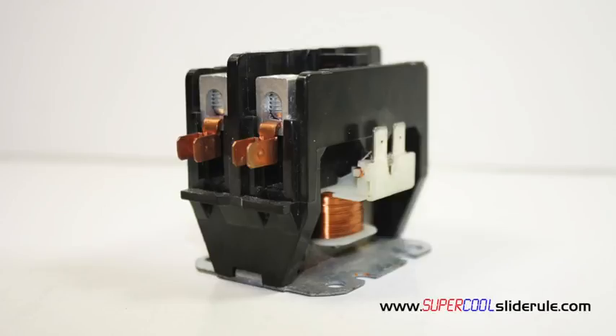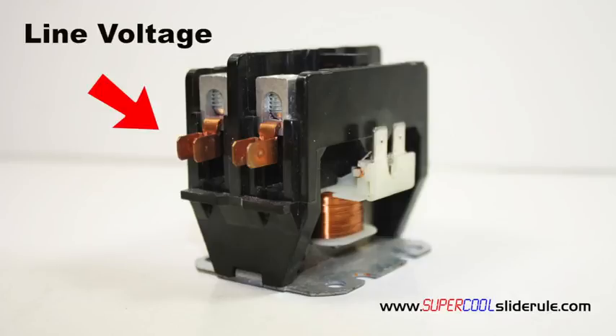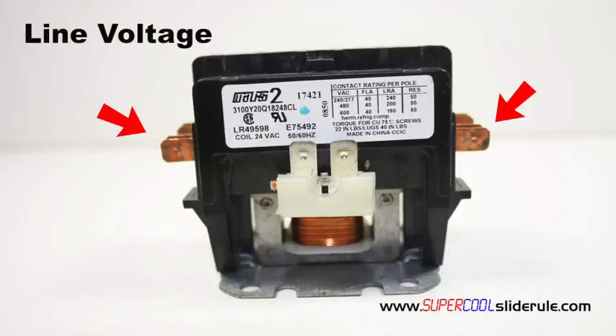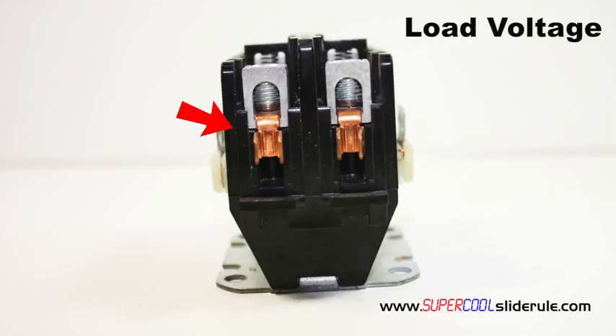In this tutorial, we will learn what a contactor is and how it works. A contactor is a control used to supply electricity to any device. The way it operates is line voltage is supplied to either side of the contactor, at the points here or on the opposite side here. The line voltage at these locations can be any voltage you desire. Next, the load is connected to the opposite unused side at these locations.